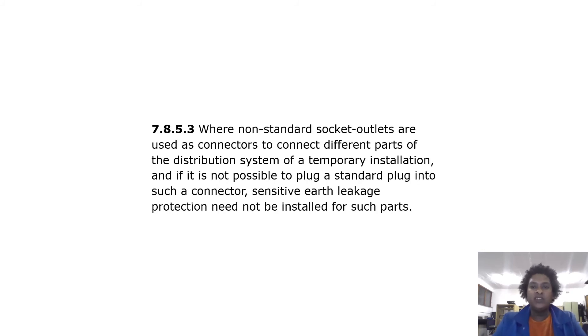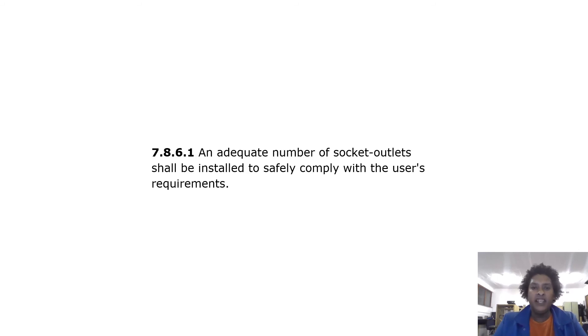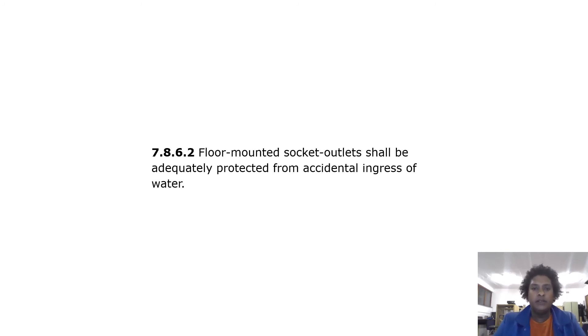Where non-standard socket outlets are used as connectors to connect different parts of the distribution system of a temporary installation, and if it is not possible to plug a standard plug into such a connector, sensitive earth leakage protection need not be installed for such parts. An adequate number of socket outlets shall be installed to safely comply with the user's requirements. Floor-mounted socket outlets shall be adequately protected from accidental ingress of water.